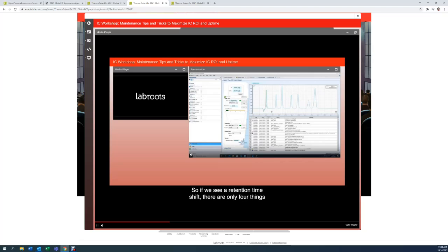If we see a retention time shift, there are only 4 things that really can affect the retention time on the column of the system. The first thing is the actual flow rate that we've set the pump at. We can see here it's set at 0.25. Are we sure it is actually pumping at 0.25? The next thing is the temperature. The next thing would be the column and the eluent. So we've got flow rate, column, temperature, and eluent. Those are the 4 things that are really going to be affecting your retention time.